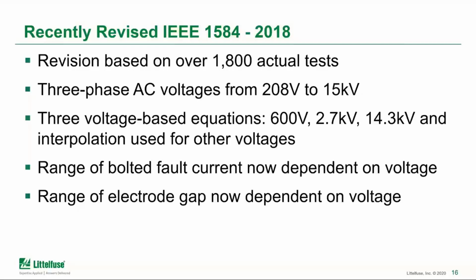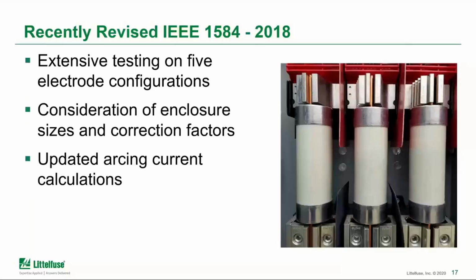And there is a range of bolted fault currents that are now dependent on those voltages, as well as electrode gap values that are now also dependent on voltage. So there are tables provided in IEEE 1584 that give those ranges, and those are now dependent on the voltage levels. One of the most significant changes, I think, is the different electrode configurations. Through the testing, depending on how the electrodes were positioned, there can be 2 or 3 times the incident energy produced from the arc jets that come out of the bus when there is an arc across the bus. So that has a really significant impact.